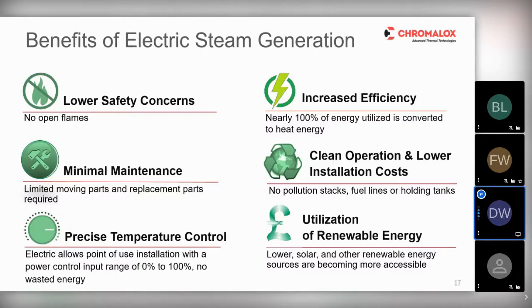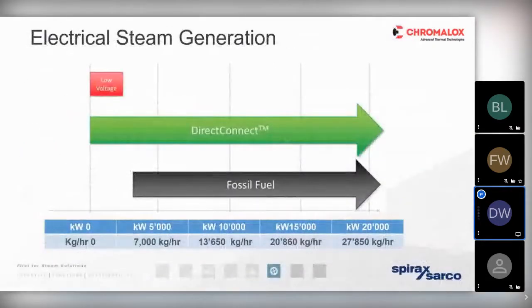And we know that we can minimize that downtime, the testing and supervision requirements, if we can move towards generating steam from an electrical element, largely down to the fact that it's got zero moving parts. It's also going to be easier to fully automate that boiler house. So a medium voltage system is an ideal solution for steam using plant that are going to have a requirement for around about 880 kilowatts or greater.